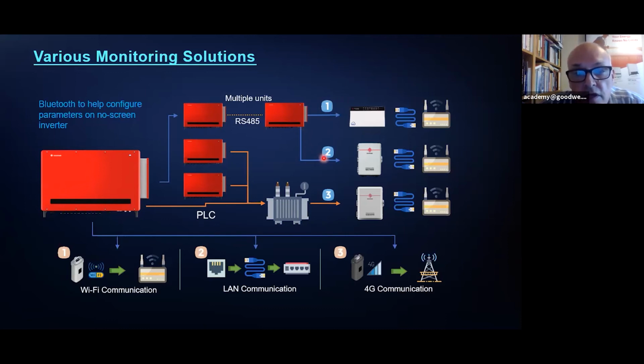Option 2: again all the inverters are connected together via RS485, but now connected into our ancillary device called the SEC1000. This isn't just data monitoring - it's also where we can achieve export limitation and power factor correction. Within this device is an EasyLogger Pro plus smart metering, and you connect CTs into this box to monitor the power at the incomer of the building.